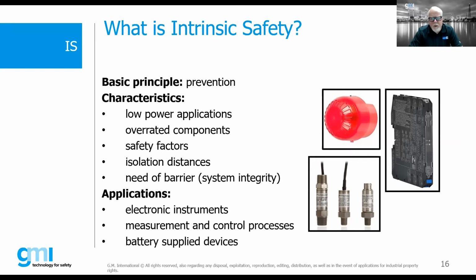Every now and then somebody will ask about wanting to do intrinsically safe motor controls or intrinsically safe lighting. Generally speaking, you're really limited on the amount of power, so you really cannot make some of those types of devices intrinsically safe. We're really limited to measurement and control devices, but transmitters, thermocouples, sensors, all of those can be made intrinsically safe.